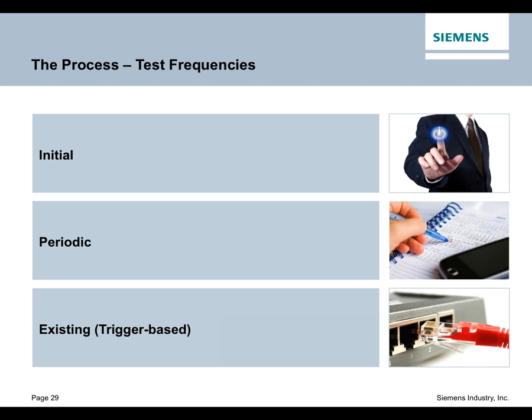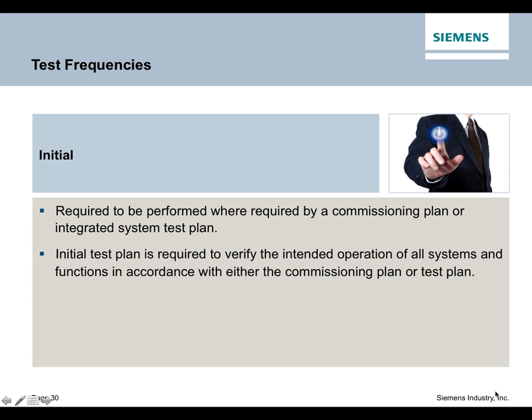Traditionally, every contractor is going to pre-test and certify their own system. The fire alarm system is going to get certified and pre-tested, same with the sprinkler system, same with the HVAC control. What this requirement now in NFPA 4 is going to require is the formal end-to-end acceptance testing. And you know what? That can often be done at the same time you're doing the fire department walkthrough, or maybe an owner's or consulting engineer's walkthrough. It doesn't mean we have to do a whole other series of tests. These things can certainly be incorporated into some of the same testing frequencies, but it just needs to be identified, documented, and handled in accordance with that.